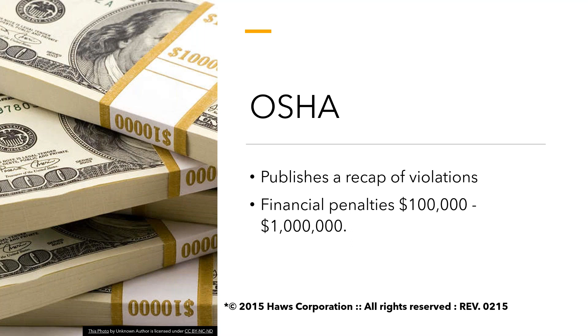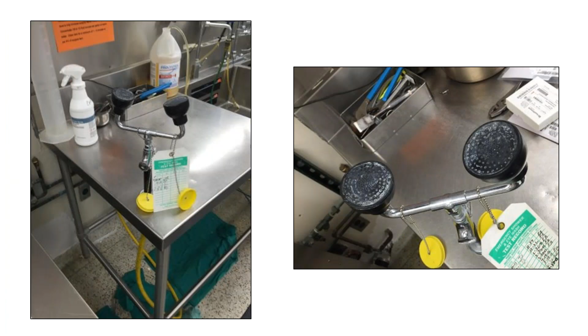Here are a couple more examples. Eye wash stations are not supposed to be located in decontamination sinks—you shouldn't be flushing your eyes where instrument decontamination is happening. That's incorrect in this picture. On the right, there's another issue: it's supposed to provide continuous flow, so you can flush your eyes hands-free for 10 minutes. Eye wash stations that don't allow that are no longer acceptable.